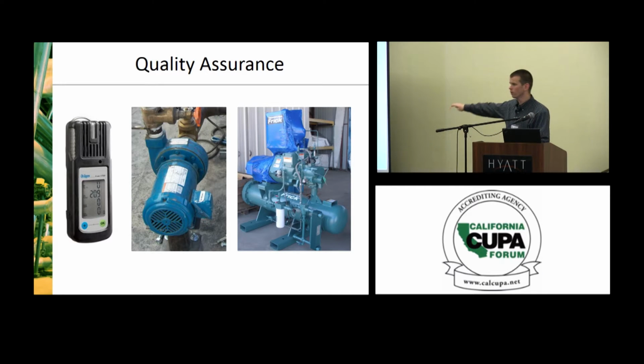Okay? Oil is another thing. Quality assurance on existing equipment, oil management. The mixing of oils can cause huge problems. Start mixing various oils with various properties, or you get someone with a car mechanic background, confident that he could rebuild anything, who puts automotive oil in or something screwy. You could be facing some big problems with your system that can lead to a system failure. So knowing what kind of oil your system has and uses is important, and that it's maintained consistently.